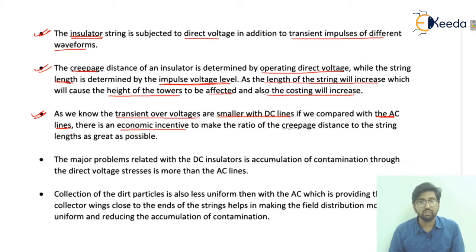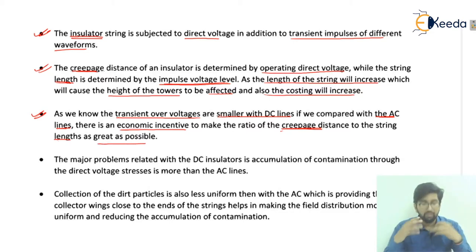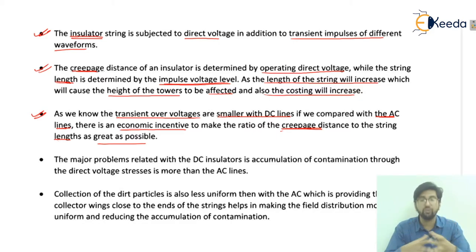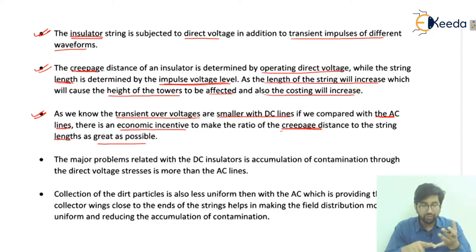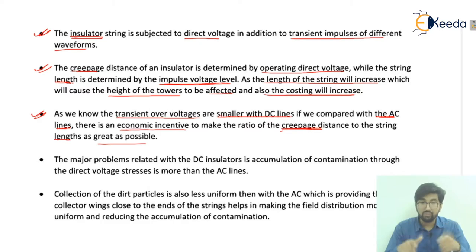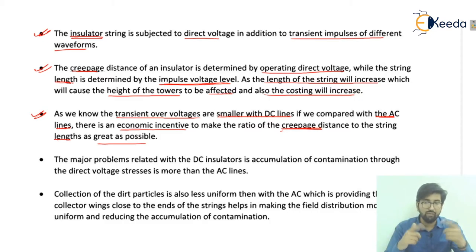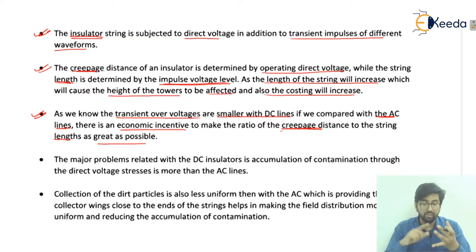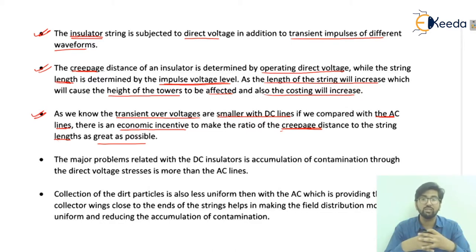There is an economic incentive to make the ratio of the creepage distance to the string length as great as possible. If we are designing insulators for DC lines, the simple thing we need to know is that if the ratio of creepage distance to string length is more, then it will be economical. Otherwise the costing increases due to the height of the tower. We have to maintain this ratio to keep the economic incentive.